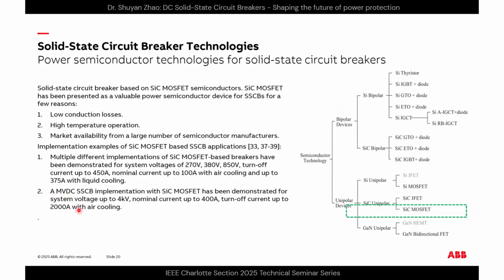A medium voltage DC solid breaker implementation with SiC MOSFET has also been demonstrated for system voltage up to 4 kilovolts, nominal current up to 400 amps, turn-off current up to 2000 amps, with air cooling -- all passive air cooling.